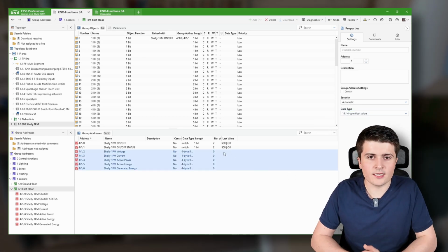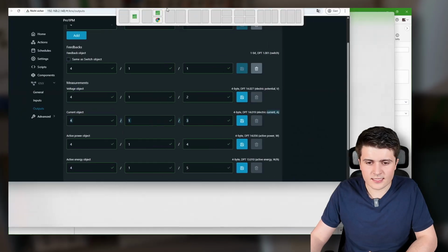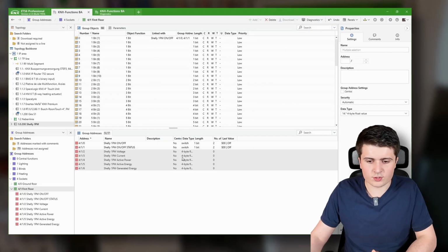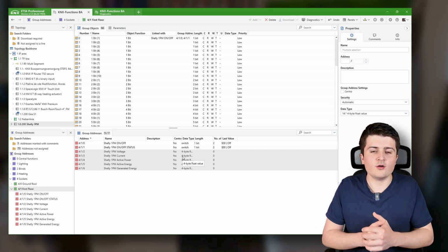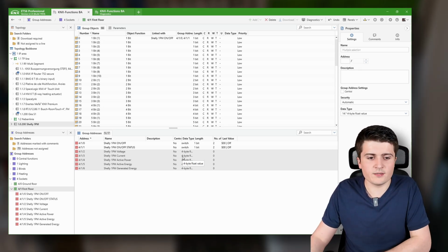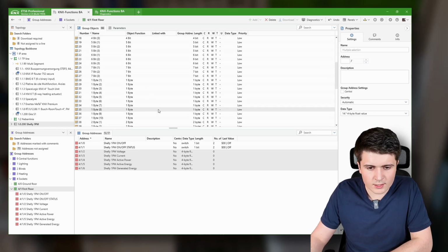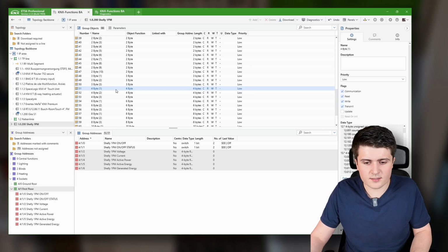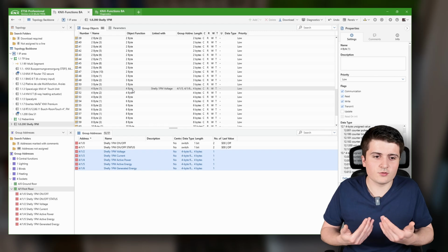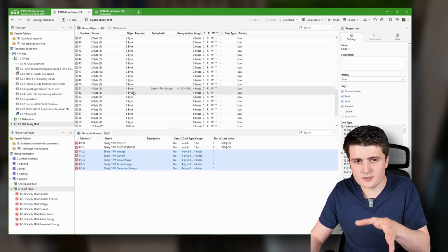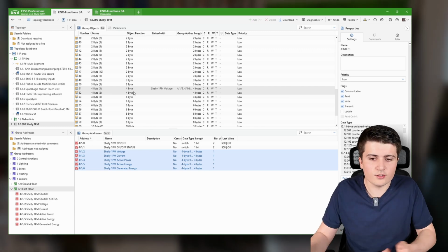Now you can also go ahead and set it to the real data point type Shelly is using here. In my case, I simply want to set it to this 4-byte value so that I remember that this is a 4-byte value. And now I will use a 4-byte value from my dummy device here and simply connect all those group addresses to it again, so that the ETS knows that these group addresses are used.